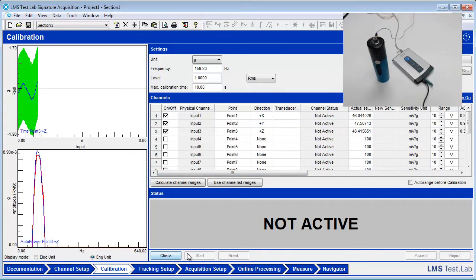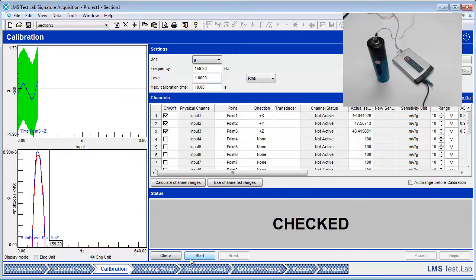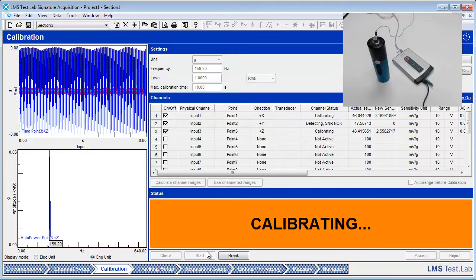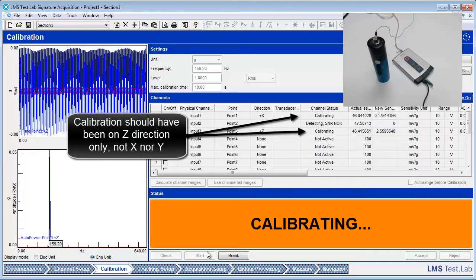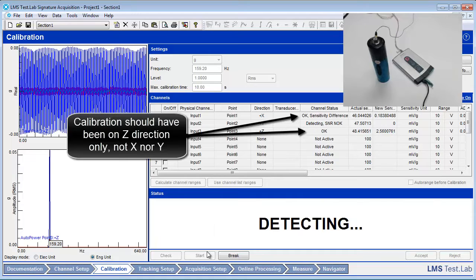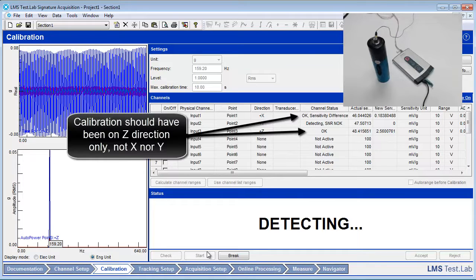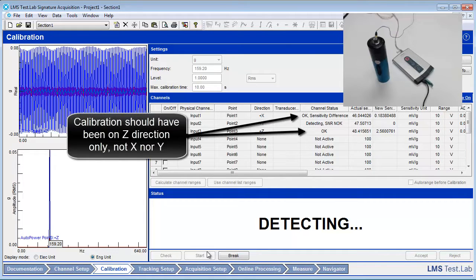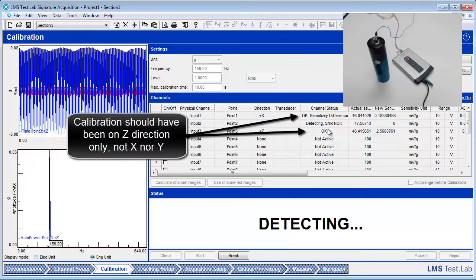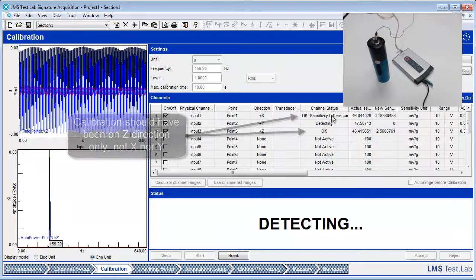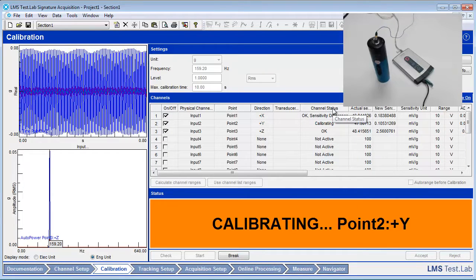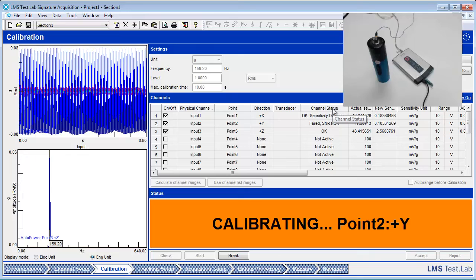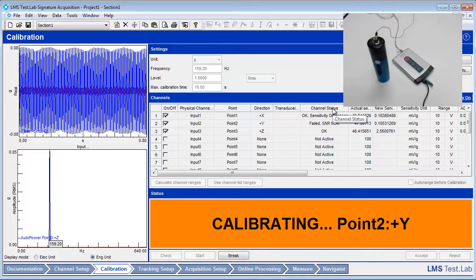Select the check button and then the start button. Notice that even though we are calibrating the Z direction, the X direction is also being calibrated. The Z direction has a channel status of OK, and the X direction has a channel status of OK, sensitivity difference, indicating a possible problem with the calibration on this channel. This message is important.